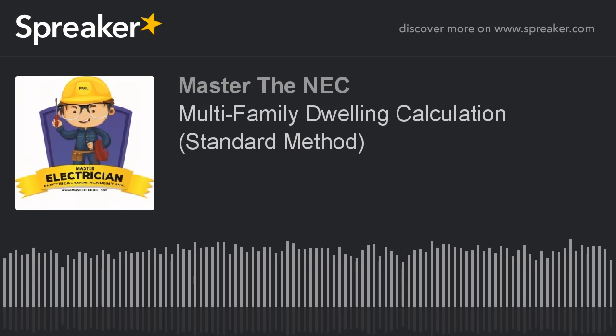Now, what about that neutral conductor? So this is quite interesting. The neutral conductor, you typically do the same way, except that first things first, we need to come up with whatever the ampacity would be. Since we're dealing with single phase, remember our neutral load was 117,462 divided by 240 equals 489 amperes. Quite a bit less than the 1,166 for the service conductors, right?